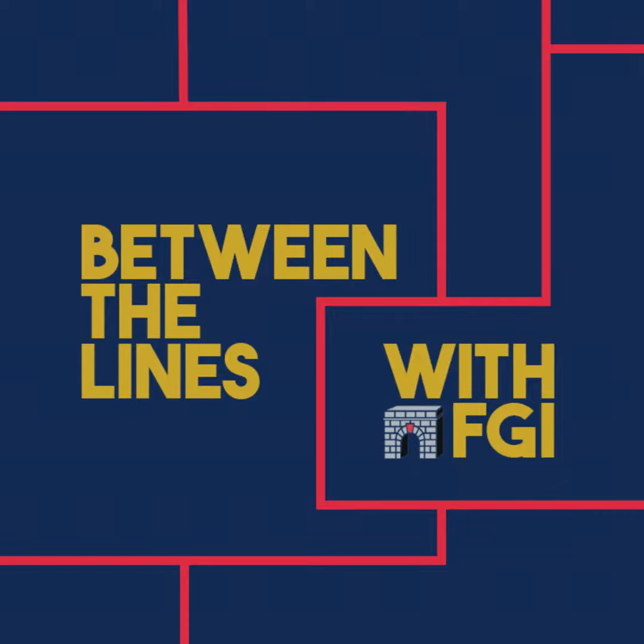And then thirdly, in a significant quench pipe failure situation where the room becomes pressurized, we want to have a pathway for that pressure to escape that doesn't involve the doorway coming and going out of the room. So that could be a vent, an opening with some sort of waveguide. It could be a blowout plug, maybe, that when it reaches a certain pressure, it pops out, and all of that atmosphere has a way to get out.